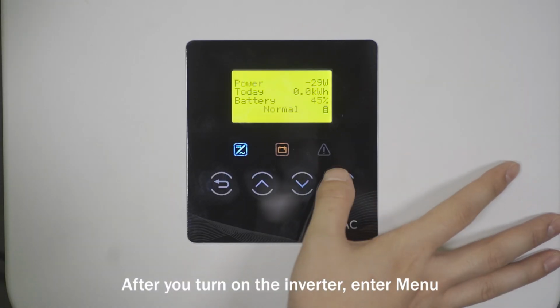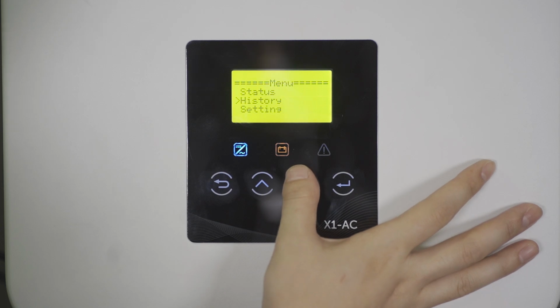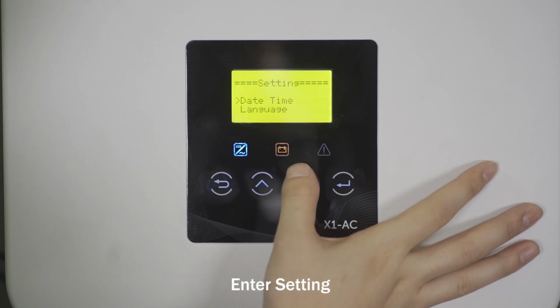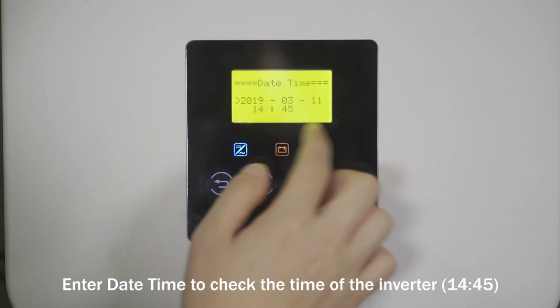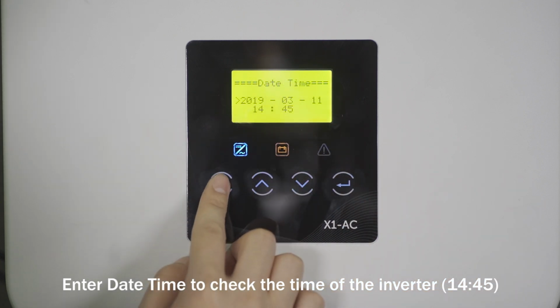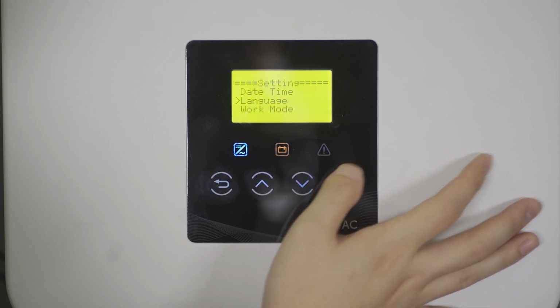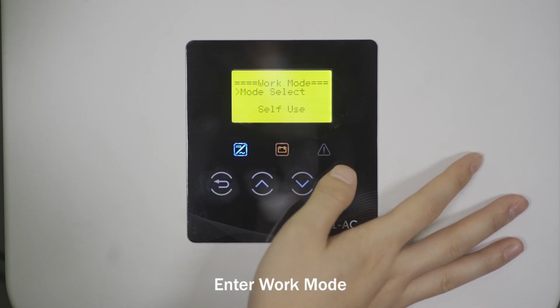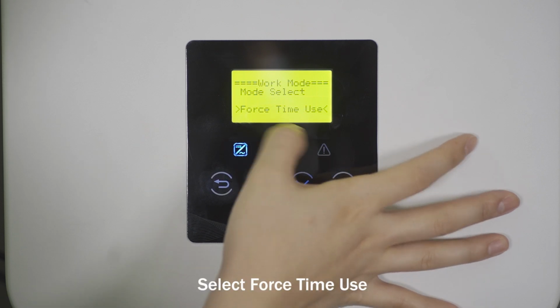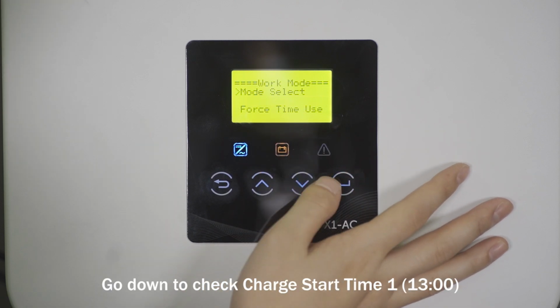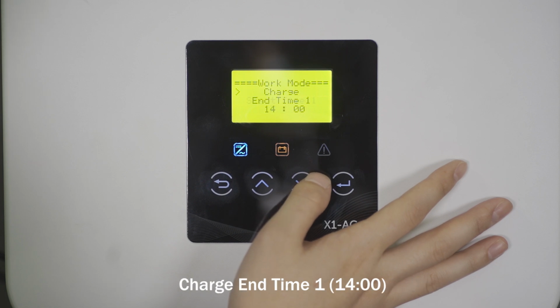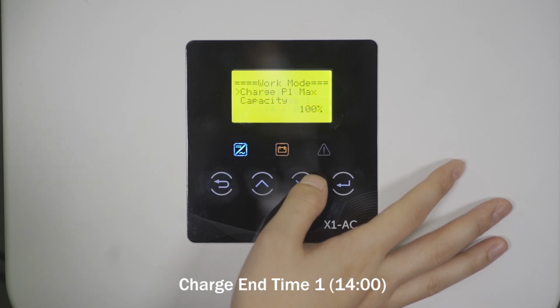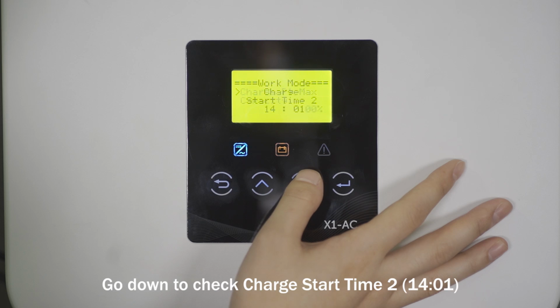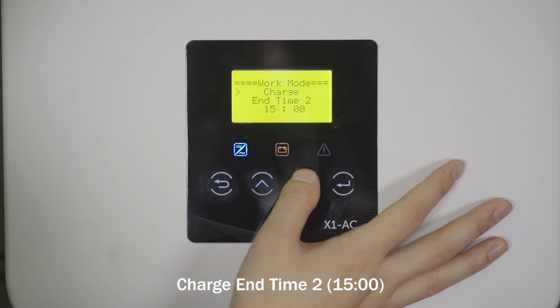After you turn on the inverter, enter menu. Enter setting. Enter date time to check the time of the inverter. 14:45. Back to setting. Enter work mode. Select force time use. Go down to check charge start time 1, 1300, charge end time 1, 1400. Go down to check charge start time 2, 1401, charge end time 2, 1500.